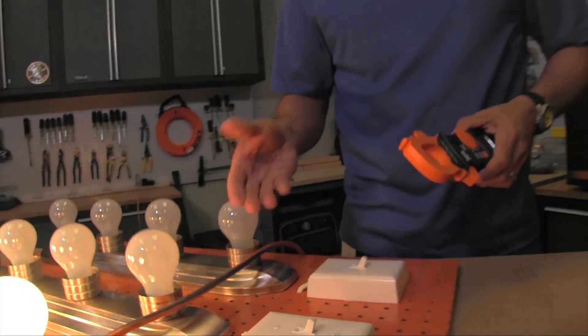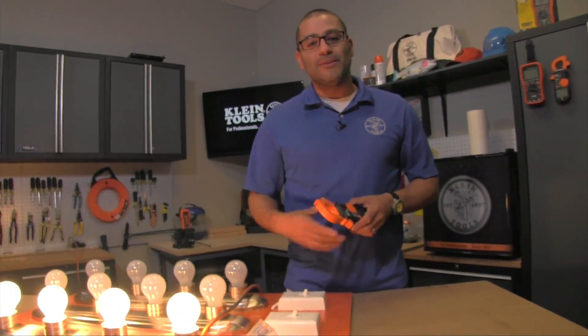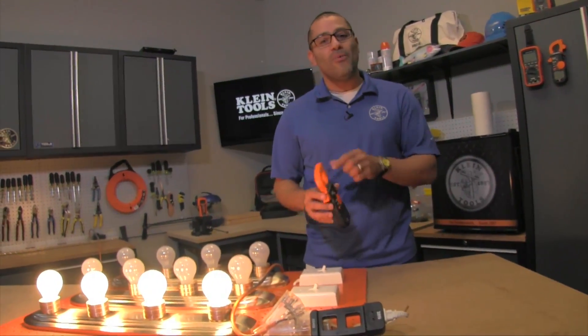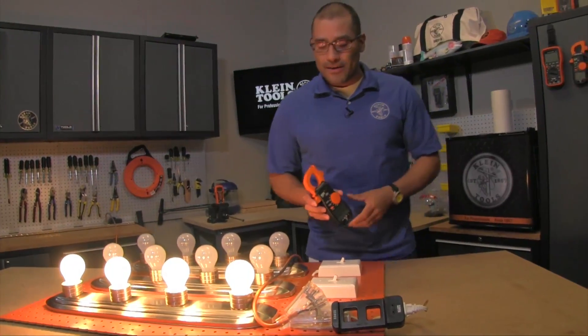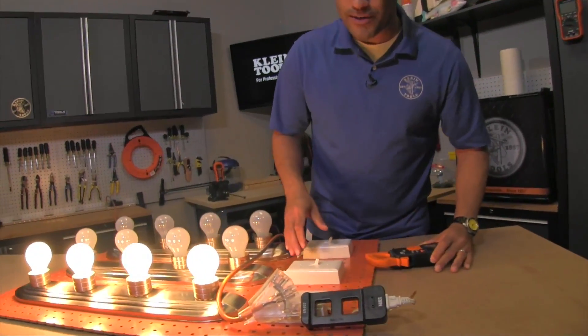in this wire you've got a hot and a neutral running through. Well, those signals will cancel each other out when the clamp meter's clamped around it. So in this case, what we would want to do is actually split the lines apart.